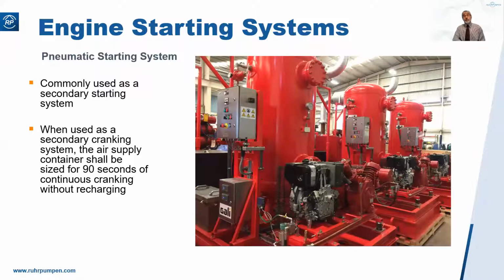Now, electric starting systems are the most common, but sometimes you get pneumatic starting systems, most commonly as a standby or backup system to the battery system. Even as a secondary system, they still need to be sized for 90 seconds of continuous cranking. So these reservoirs, these accumulators can be very big, and you'll see that later on. Here we show one, and it has a little engine-driven compressor to recharge it.